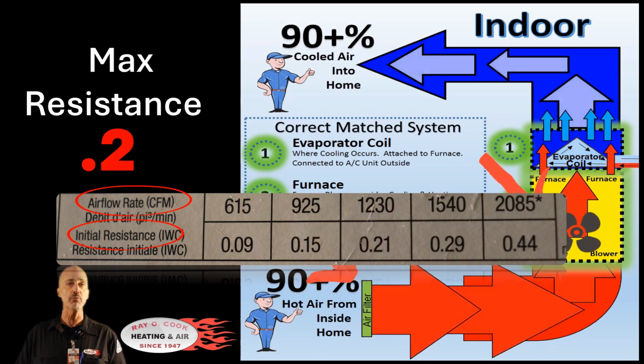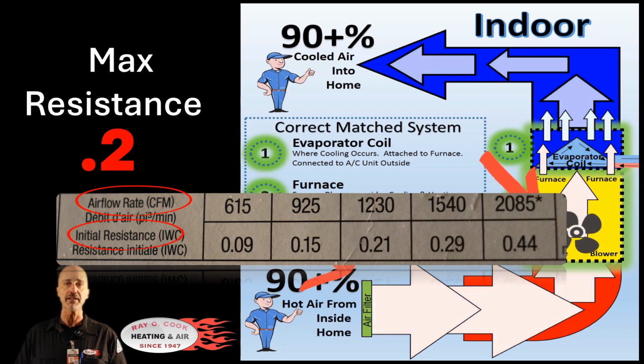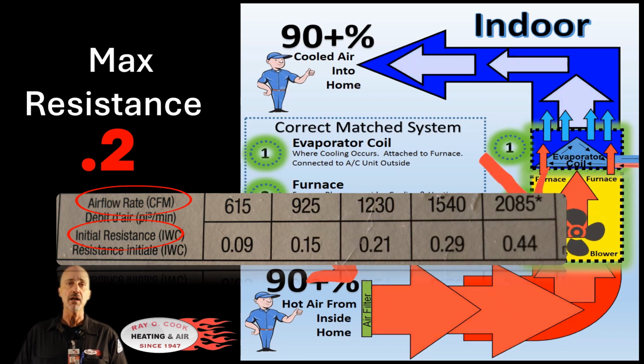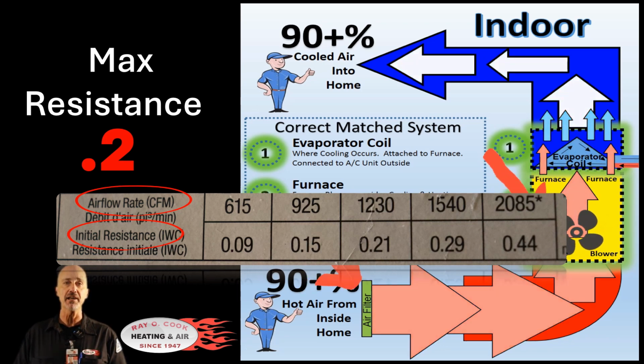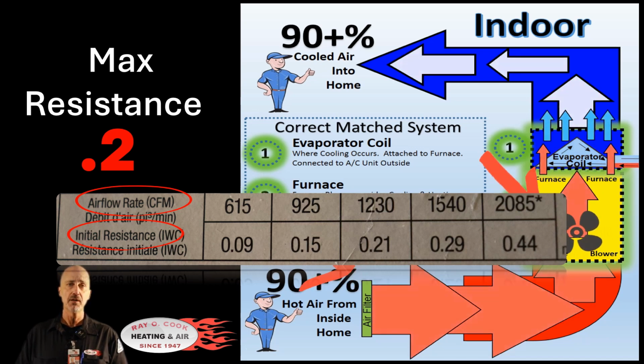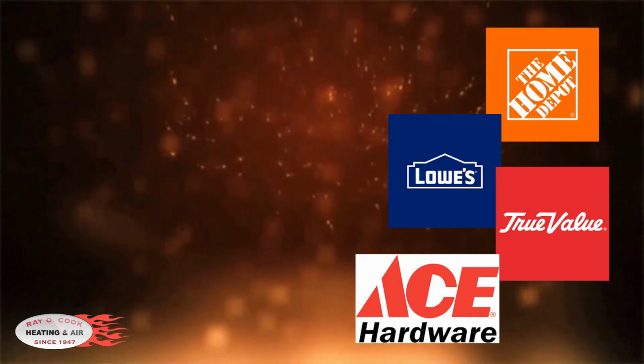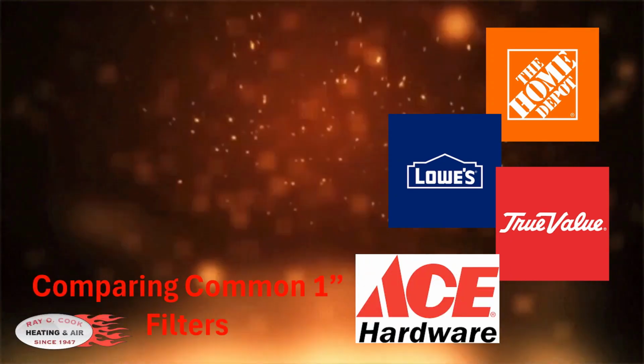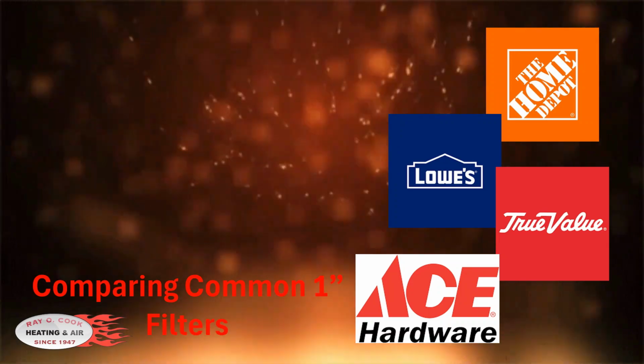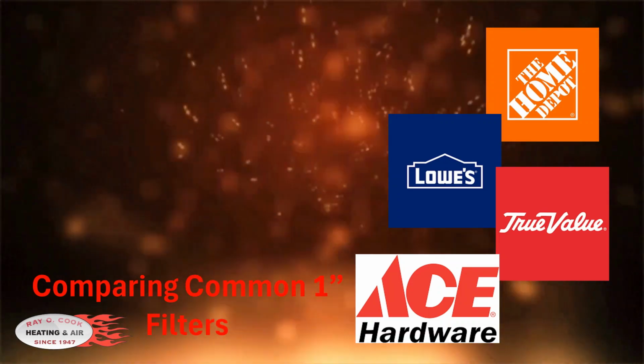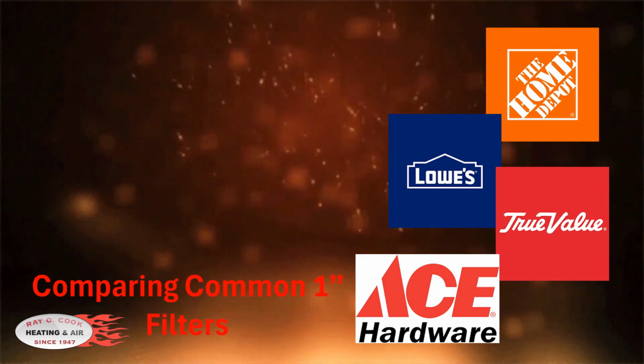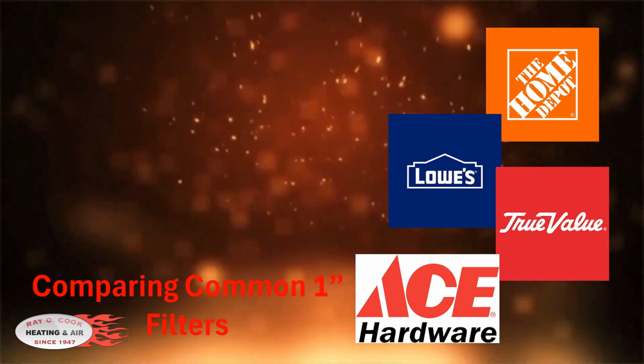We strongly suggest knowing the resistance rating and CFM flow rate on any filter that you install. Not knowing is a guess, and you run the risk of negative results with air quality and negative results on your heating and cooling equipment. So now you know how many CFM your system needs and the fact we do not want to exceed 0.2 on the filter restriction scale. So we'll take a look at some examples of filters that you would see at Home Depot, Lowe's, True Value Hardware, Ace Hardware. We'll start with one that says that it's MERV 5.